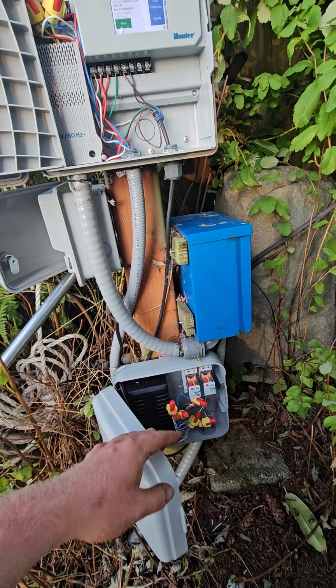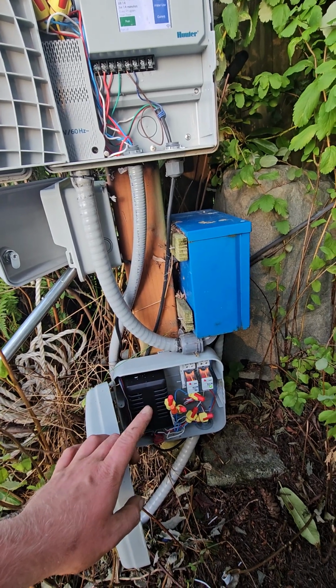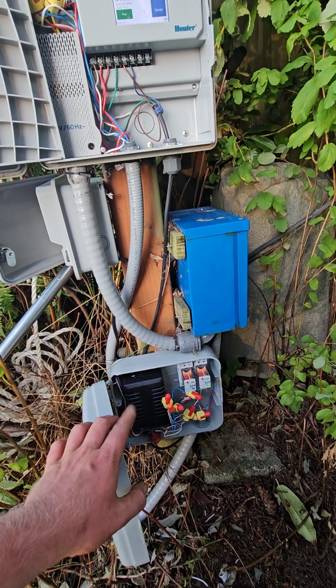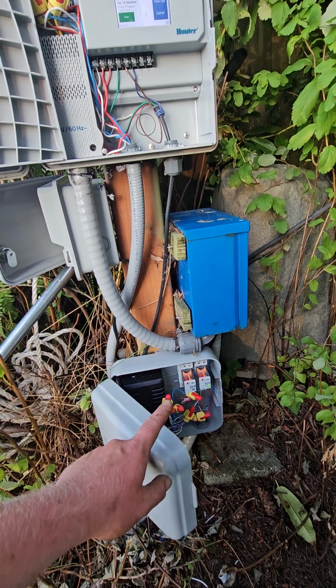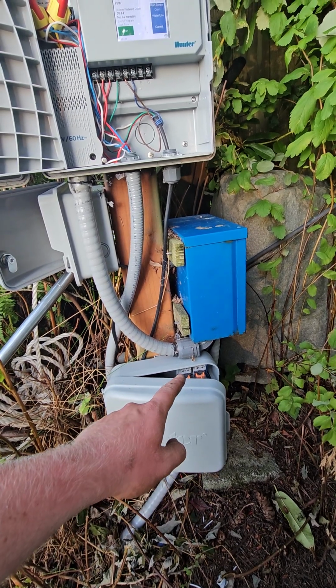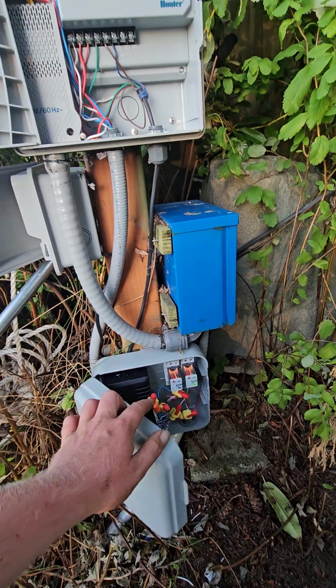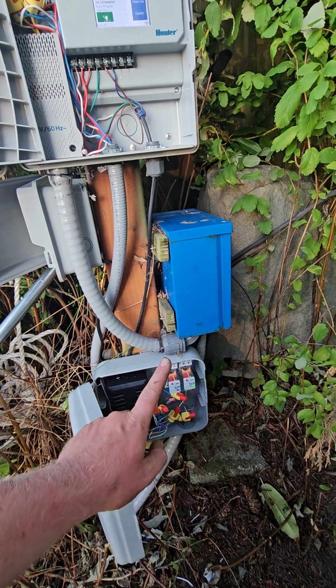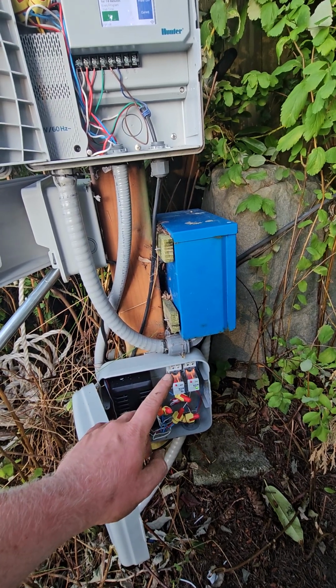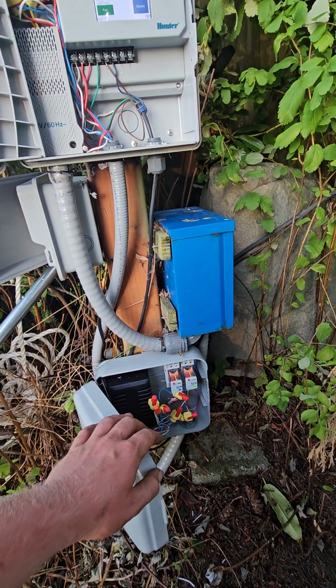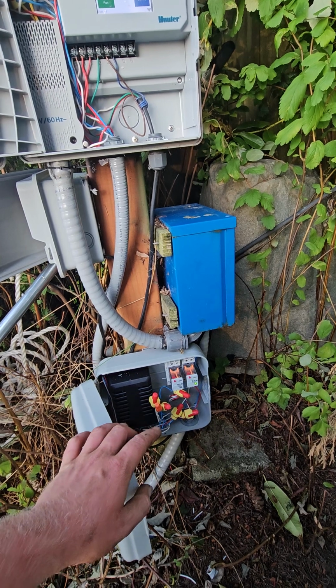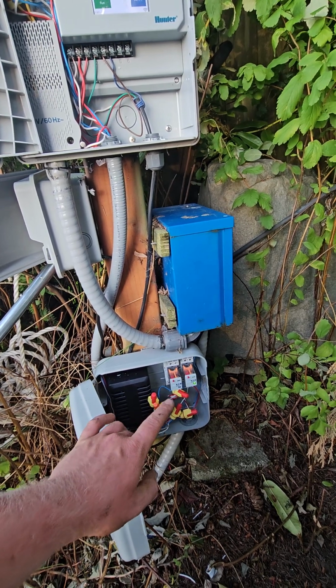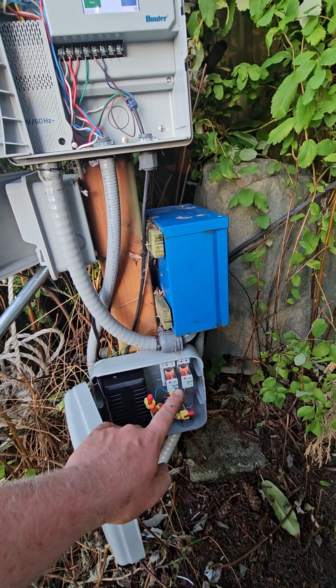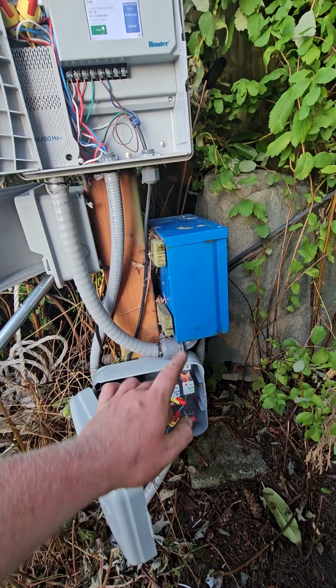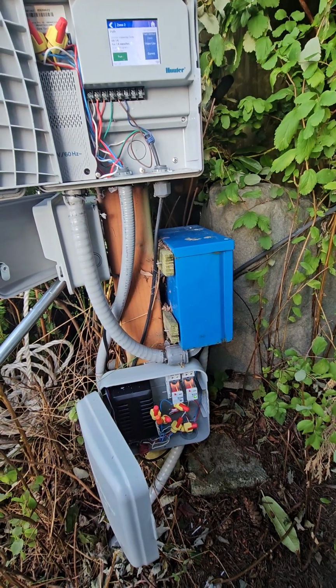Yeah, I got a blood blister on my finger. So what we have is, we've got our 24 volt UPS. We were using this relay, a 24 volt ice cube, to basically switch 24 volts out to that contactor. And originally we were going to do that and just keep the original contactor, but it just chattered still. We could never get it to not chatter. Now, the one with the green light on is basically, we have a fuse, like a 3 amp fuse, on the primary side of the transformer.